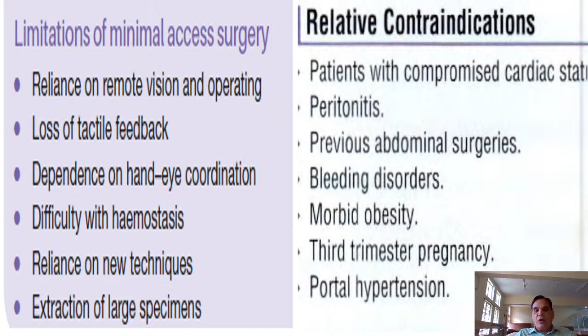In short, you must be aware of the basic laparoscopic technique. Just try to remember a few important things. What are the common instruments used? Remember 3 or 4. Laparoscope. Laparoscope is of two types. First is front viewing, another is side viewing. It has a 0 degree or 30 degrees. 0 degree is most commonly used. The light source is a cold light source, either halogen or xenon. We are commonly using a halogen lamp.